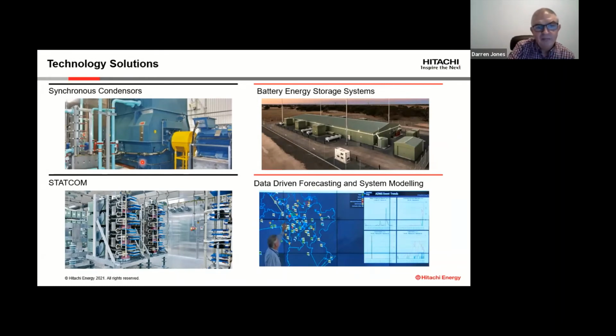Synchronous condensers are basically just a large electric motor inside this box, and they often come with a flywheel. It's that big flywheel, the physical mass connected to the synchronous condenser, that provides this inertia, using the kinetic energy stored in that rotational mass to inject into the system in times of fault. Synchronous condensers are driven by what's called a pony motor. You might see there's a small motor that drives this larger motor up. They don't generate any active power, but synchronous condensers can manipulate power factor. The stator and rotor circuits can be either over or under excited to produce either leading or lagging power factor. So as well as inertia, they can provide reactive power services onto the grid.